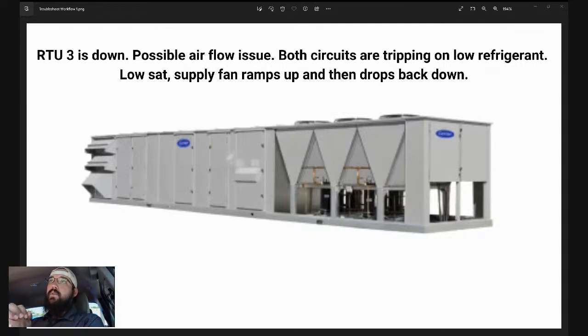So yes, my push here is for the troubleshooting process to be mindful of what's going on and what's happening in our mechanical system, so that we don't end up trying to diagnose a refrigerant issue for a mechanical problem. And some of that does come down to understanding. So he wasn't aware that 30 hertz was so detrimental to your heat load on the system. Now, if 30 hertz in that scenario, given the context, if we were in the middle of winter, maybe a different story. We're in the middle of our summer. So 30 hertz, 40 hertz, we should rarely see those numbers on any of our supply fans. There's way too much load, especially for a system that's been down. So that's one of those indicators to help steer you on where do you go next and what's the next right step.